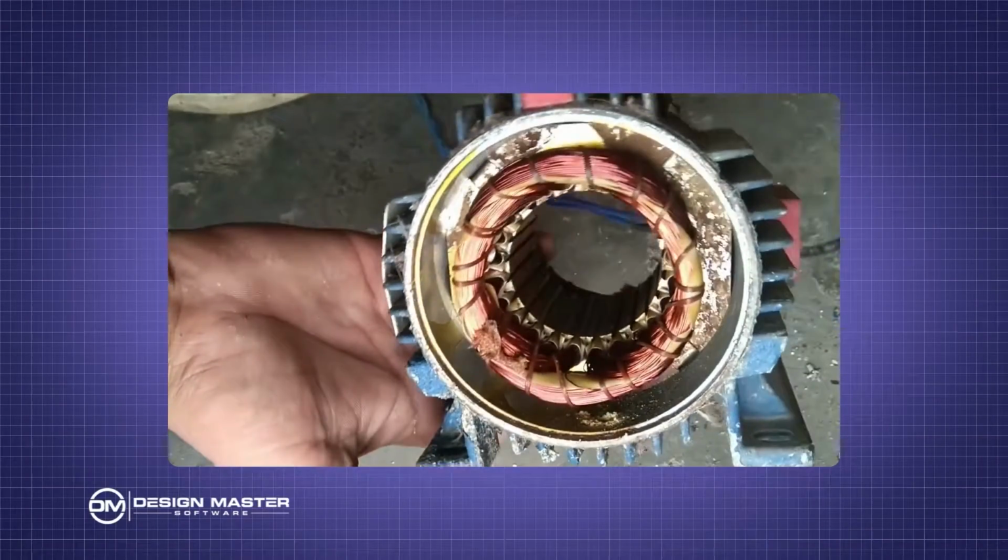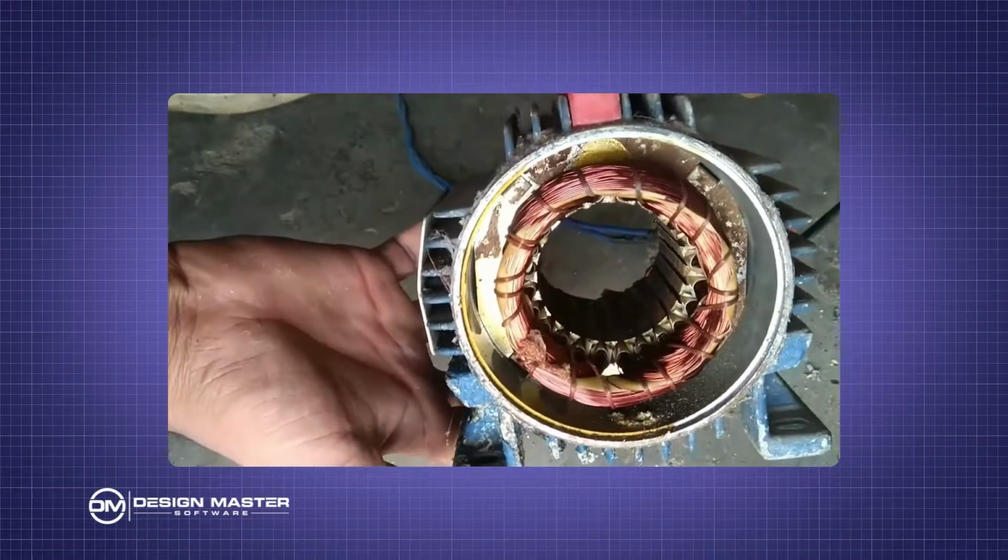Well, you can take it to what the service factor says, and it may not be 15%. It may not have a rating at all for service factor. But if it does, it's okay to take the motor to that level, but it'll cut down on the life of the motor for sure because it's going to be running hot.